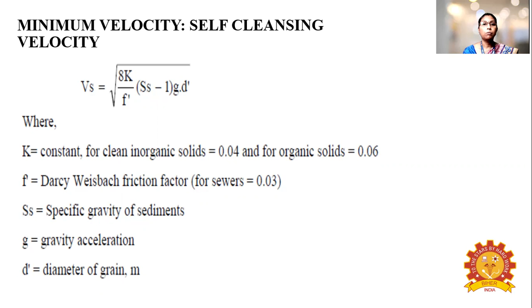Once you know the specific gravity of the solids, then the diameter of the solids or the grains we can substitute, and we can substitute the value for the friction factor and also the constant value capital K based on the solids present, and you can calculate the self-cleansing velocity. So the self-cleansing velocity plays a vital role in avoiding the settlement of the solids in these sewer lines. Otherwise, the settlement of solids will become a great nuisance in blocking the sewer lines.